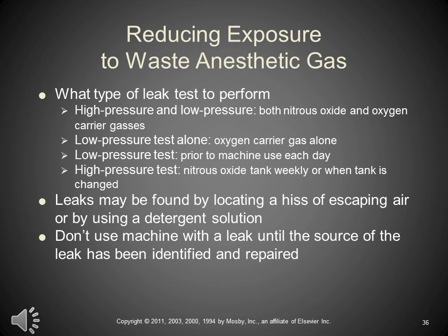What type of leak test to perform? Well, high pressure and low pressure. We're checking both for nitrous oxide and oxygen. Low pressure test alone, we're just checking for the oxygen carrier gas by itself, isoflurane, sevoflurane. We should run a low pressure test on every machine every day before it is used. High pressure tests are usually run weekly or more commonly when tanks are changed. Especially if you're not using nitrous, it's not that big a concern.